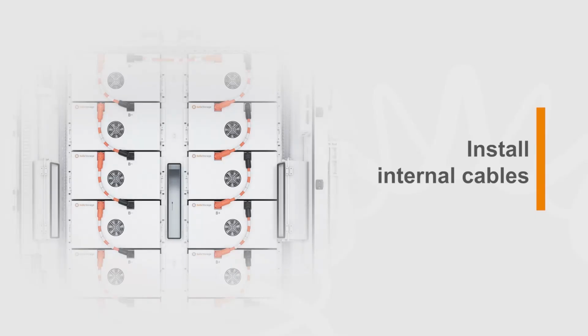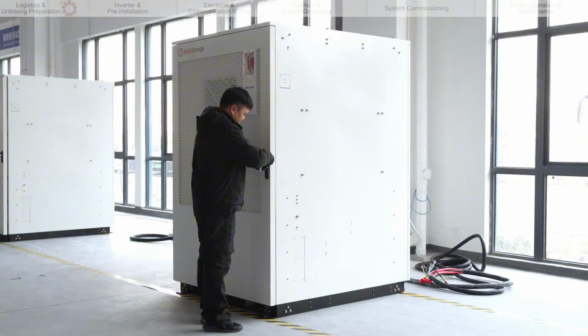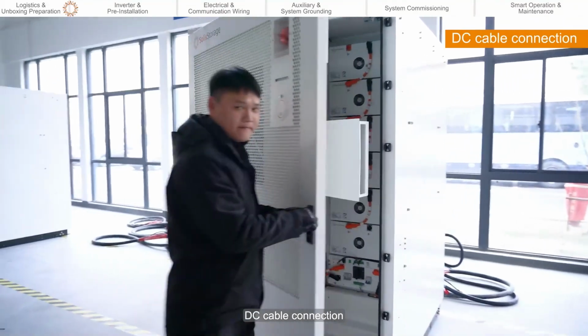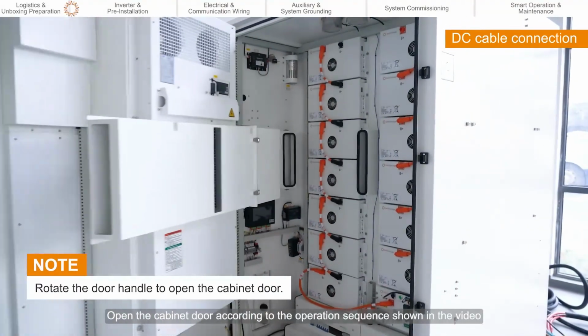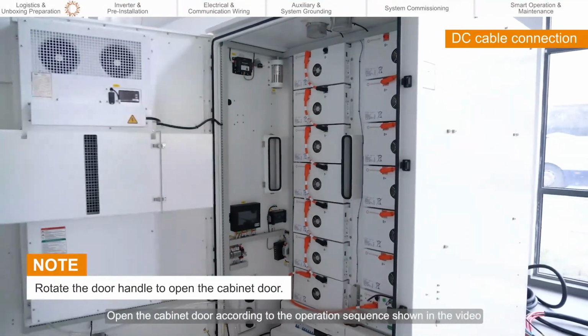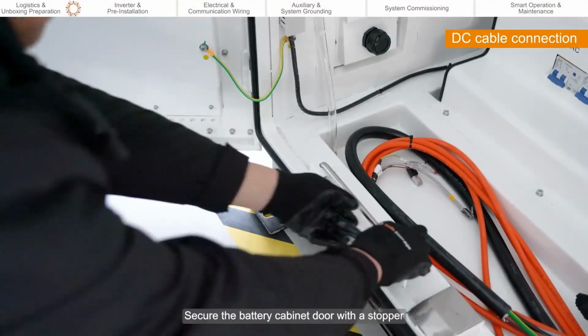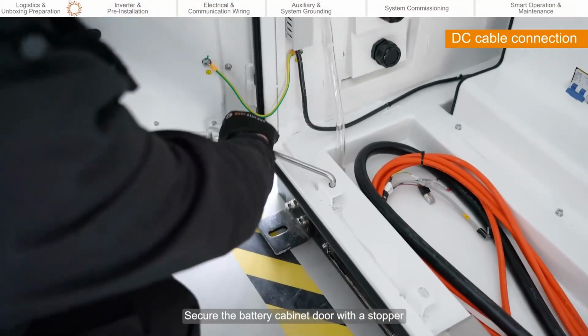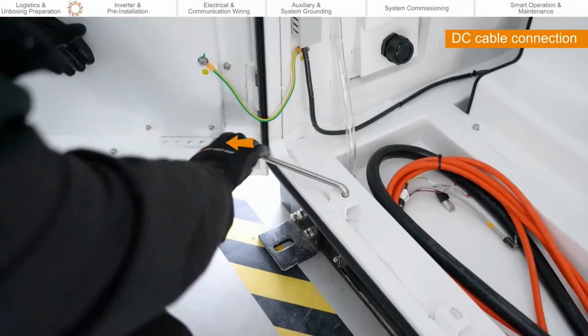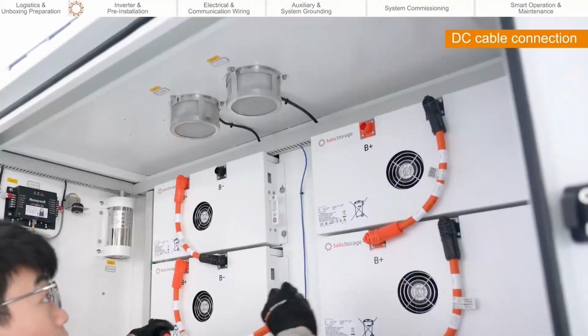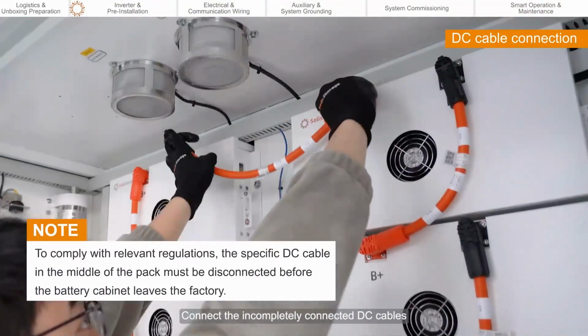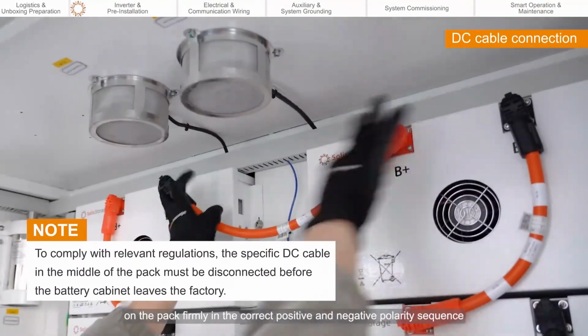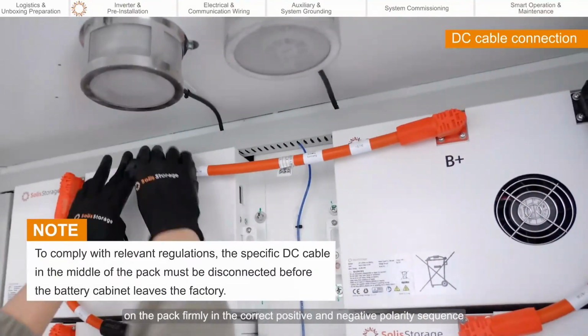Install internal cables. DC cable connection. Open the cabinet door according to the operation sequence shown in the video. Secure the battery cabinet door with a stopper. Connect the incompletely connected DC cables on the pack firmly in the correct positive and negative polarity sequence.